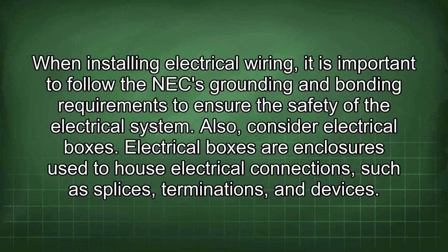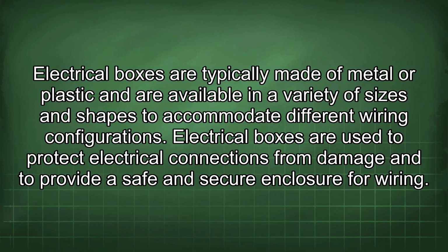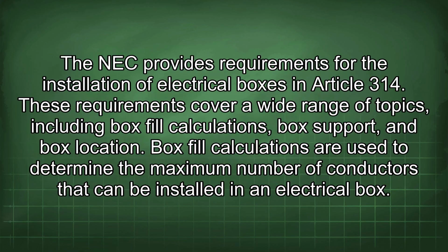Electrical boxes are enclosures used to house electrical connections, such as splices, terminations, and devices. Electrical boxes are typically made of metal or plastic and are available in a variety of sizes and shapes to accommodate different wiring configurations. Electrical boxes are used to protect electrical connections from damage and to provide a safe and secure enclosure for wiring. The NEC provides requirements for the installation of electrical boxes in Article 314. These requirements cover a wide range of topics, including box fill calculations, box support, and box location.